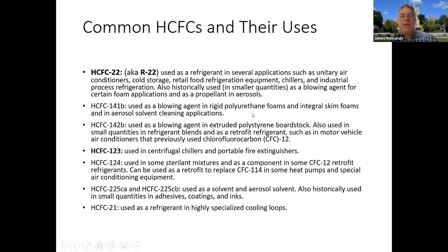You want to be planning for phase out of R22 and for the HFCs. These are some slides from a previous presentation. Here's the old schedule for class 2, and if you look at it, we're already near the bottom: in 2020, a 99.5% reduction in HCFC consumption and production from the baseline, and in 2030 it's supposed to hit 100%. You can look at this slide on your own—these are some other uses for HCFCs.